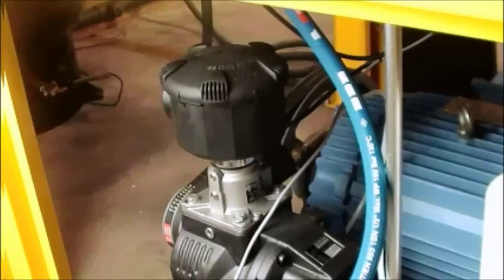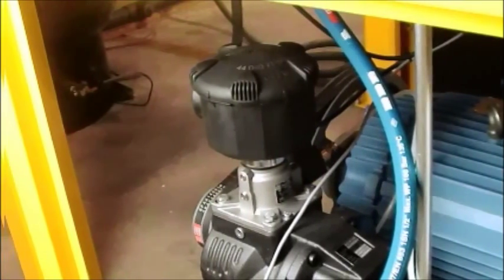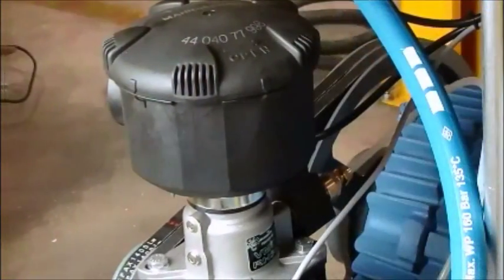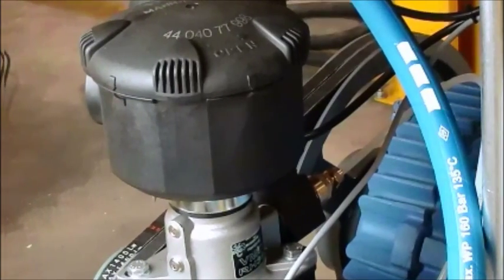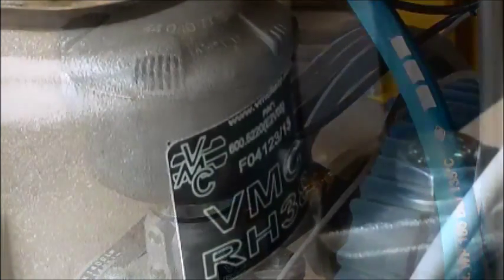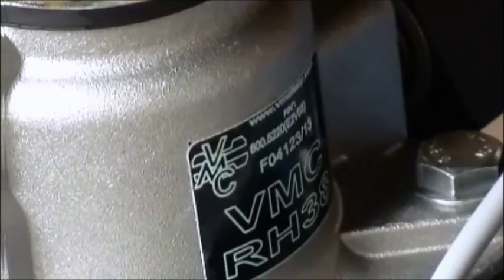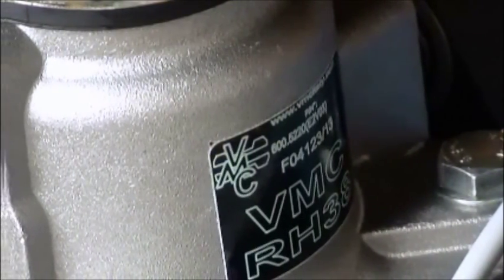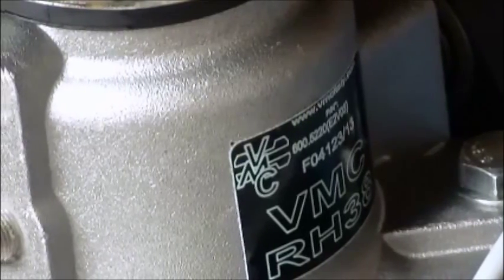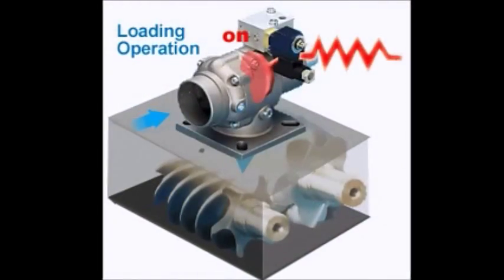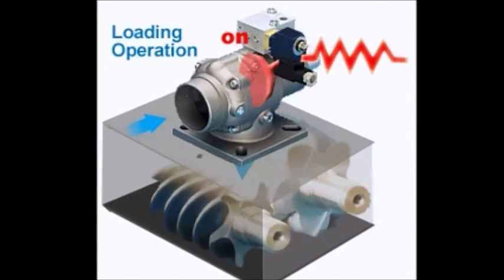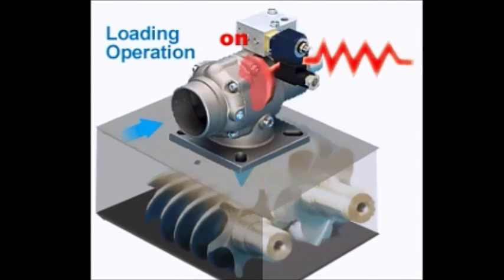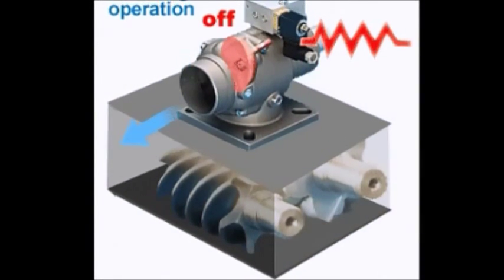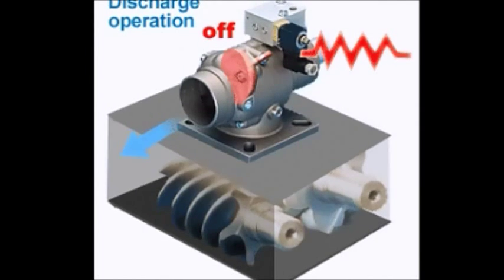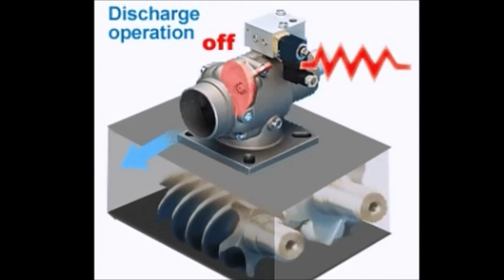Another critical component of the compressor is the air inlet valve. VMC inlet valve is installed at the inlet port of the compressor pump to control the capacity of the compressor. At the startup, the valve stays open till the control signal is applied to close the valve and restrict the compressor inlet airflow. During normal operation, the valve opens and closes in response to the PLC control signal to meet the air demand. At shutdown of the compressor, a built-in check valve automatically closes to prevent backflow of air and oil.